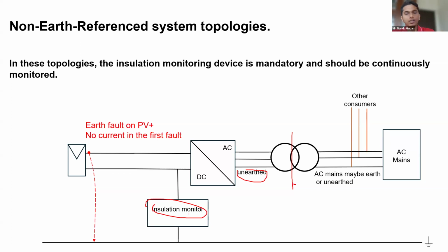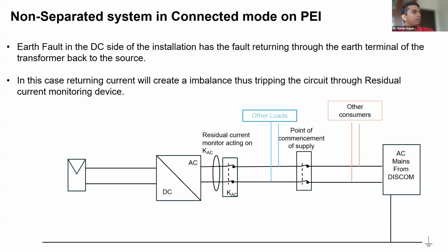And you are not supposed to have a second fault in the system. If there is any second fault, then it can be pretty complicated. So now the problem is, if you have a solar PV according to these topologies, if you have connected to a PEI, there can be a problem. So I have taken a non-separated system.